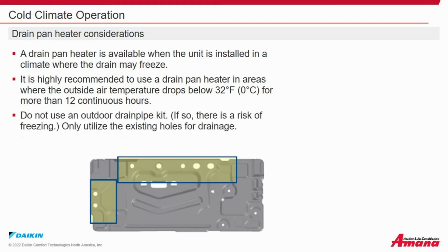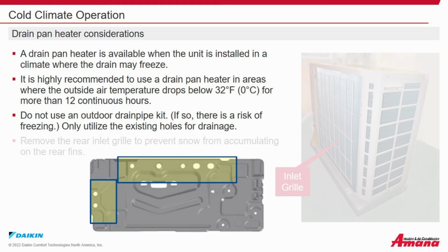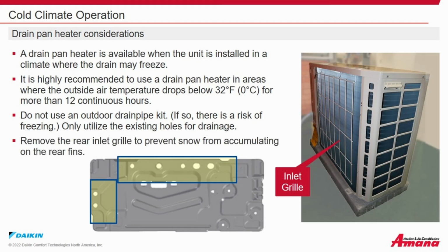Do not use the outdoor unit drain pipe kit. If so, there is a risk of freezing. Only utilize the existing holes for drainage. Remove the rear inlet grill to prevent snow from accumulating on the rear fins.